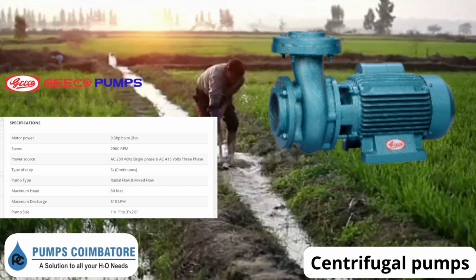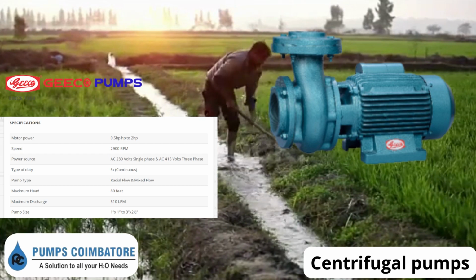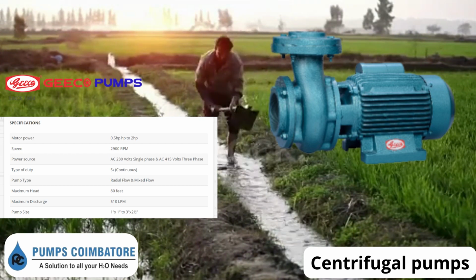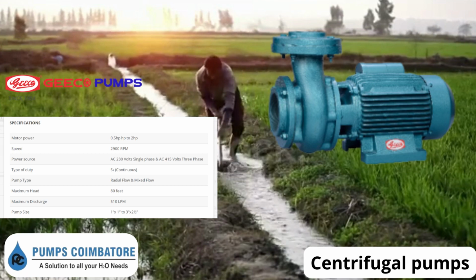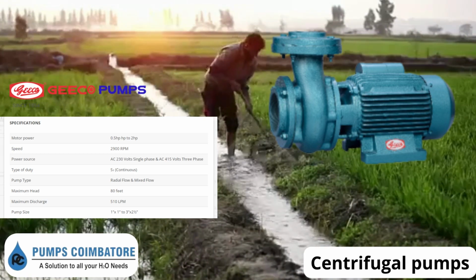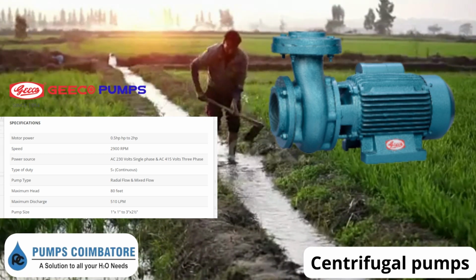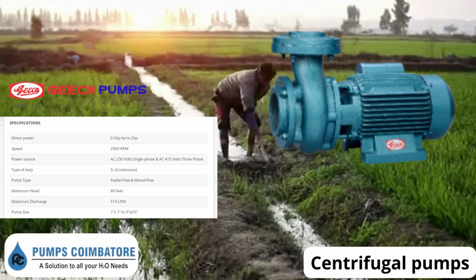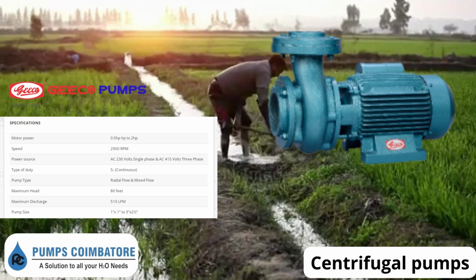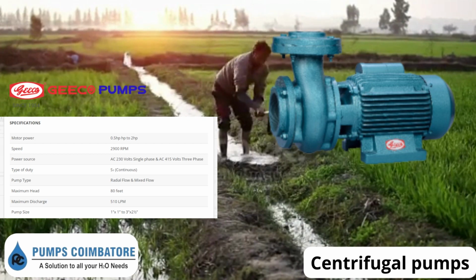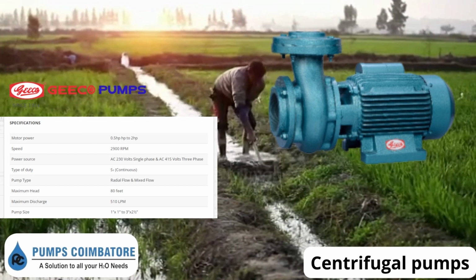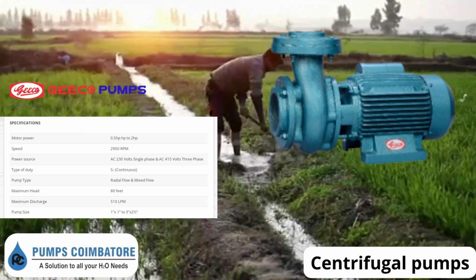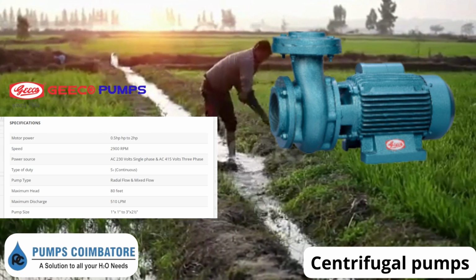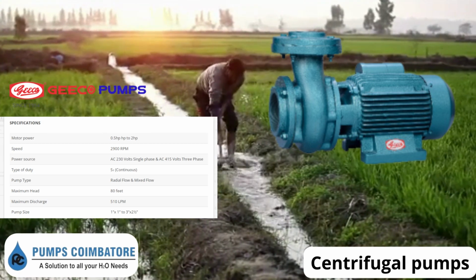If the application needs to lift water to the pump, a centrifugal pump must be used. Above ground, centrifugal pumps are commonly used with surface water sources or shallow groundwater sources. They are also used as booster pumps in irrigation pipelines. They must be filled with water or primed before they can operate. The suction line and pump must be filled with water and free of air, so airtight joints and connections are important on the suction line.